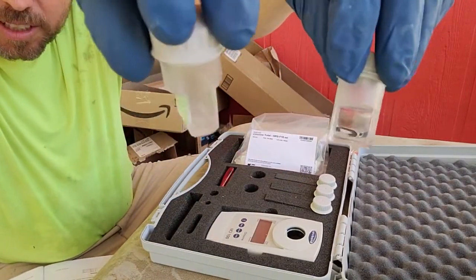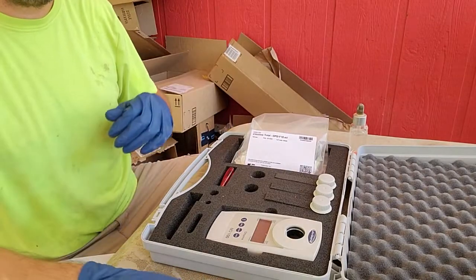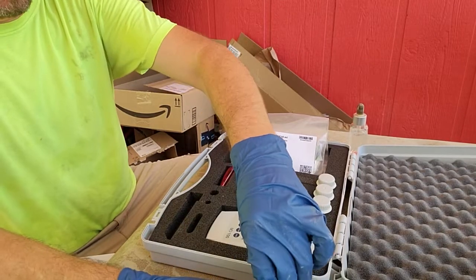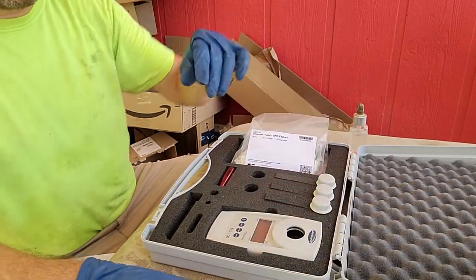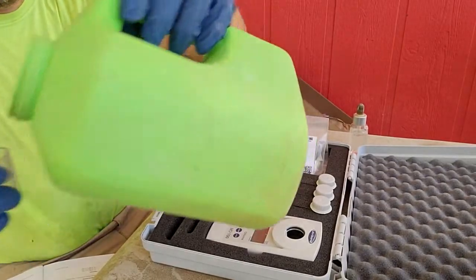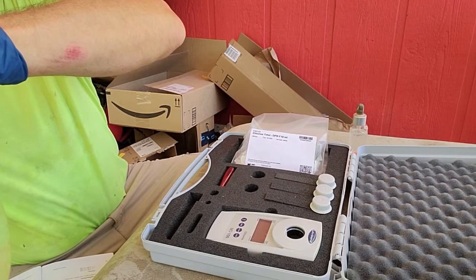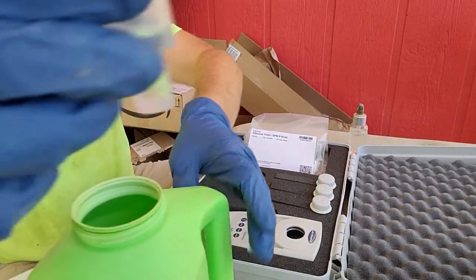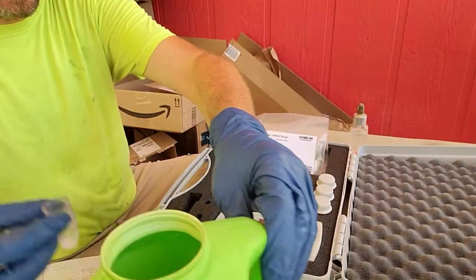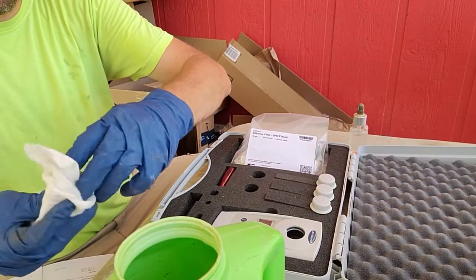They're a little different than the glass ones we've been using, but they allow us to read all the way from 0.1 up to 8.0 milligrams per liter, which is going to work out really nice.